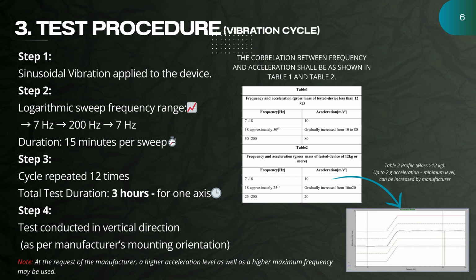Finally, in step 4, the test is performed in the vertical direction or according to the battery's mounting orientation as specified by the manufacturer. And at the bottom, the note highlights that companies may request higher acceleration or higher maximum frequencies, depending on their validation needs.